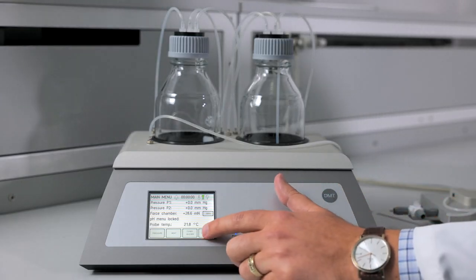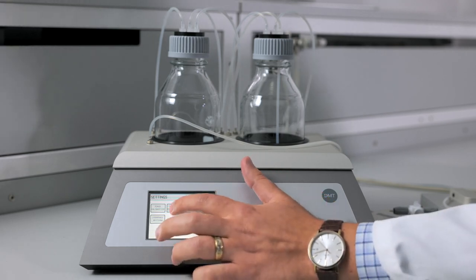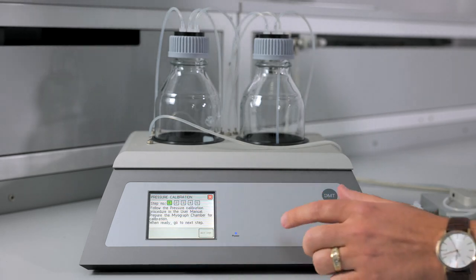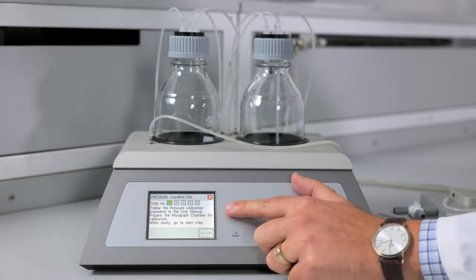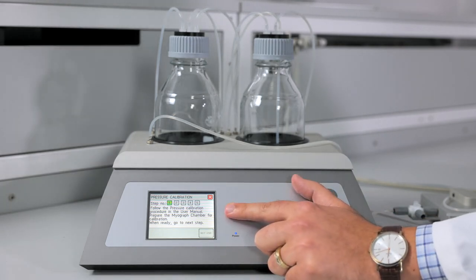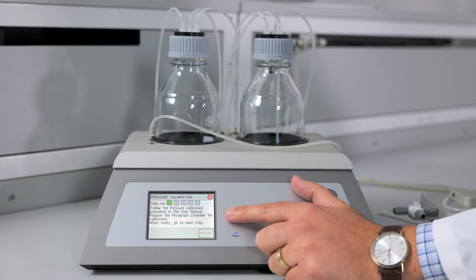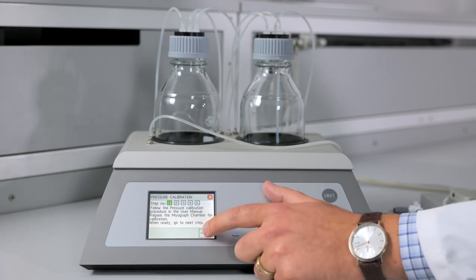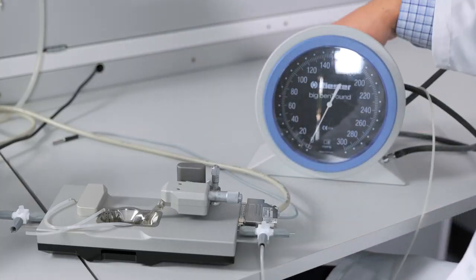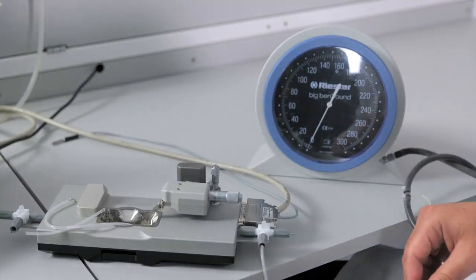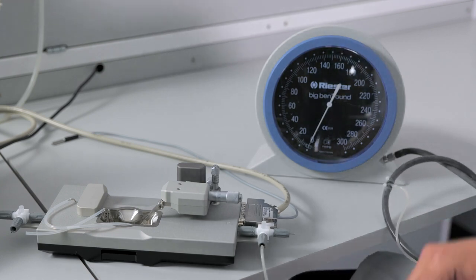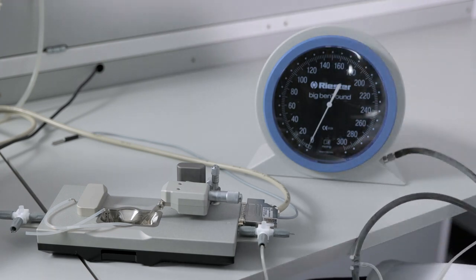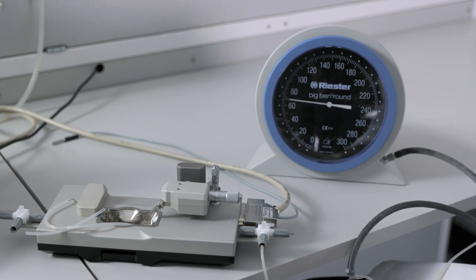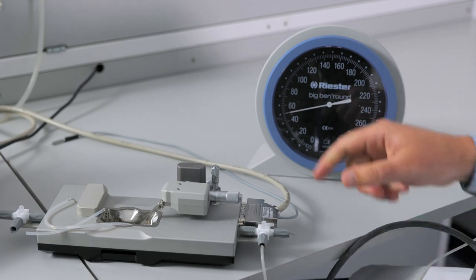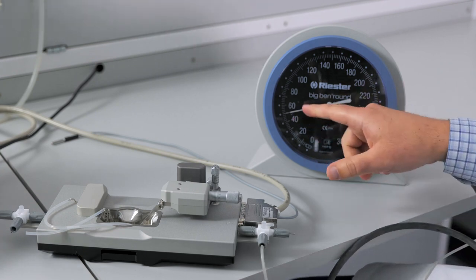We will go into the settings menu on the interface and go to pressure calibration. This says that it's a 5-step process and you should follow the procedure in the user manual. However, instructions are also provided on the touchscreen. Select next step, which will then ask us to apply 50 millimeters of mercury pressure using the manometer. So we will add that pressure. And pressure should be holding. It is here, which is good.